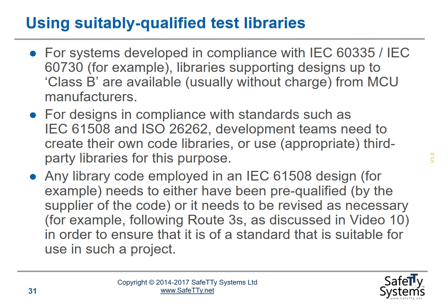Any code library employed in an IEC 61508 design, for example, needs to either have been pre-qualified by the supplier of the code, or it needs to be revised as necessary, for example following Route 3S, as we discussed in video 10, in order to ensure that it is of a standard that is suitable for use in such a project.